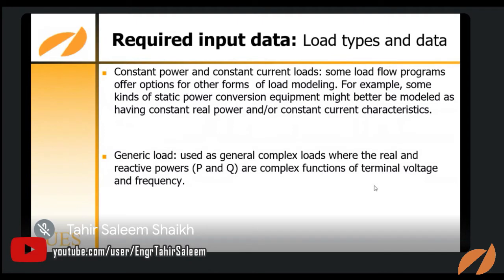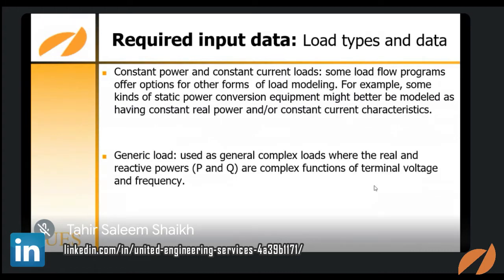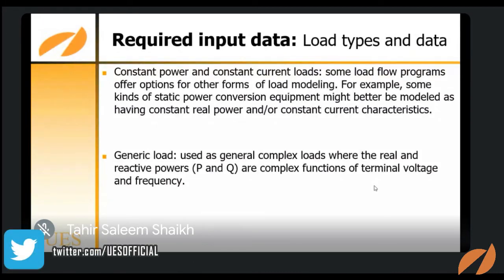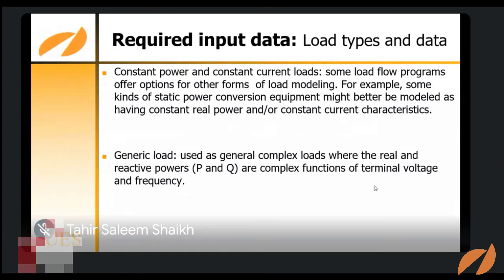Generic load is used as a general complex load, where the real and reactive power are complex functions of the terminal voltage. So these loads vary the power flow, depending upon the terminal voltage and frequency. That is totally depending upon these two electrical parameters. If the voltage and frequency of the system or of the supply change, then it will automatically affect the flow of real and reactive power.